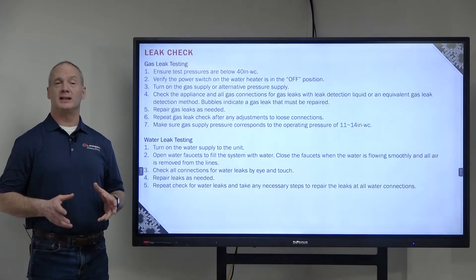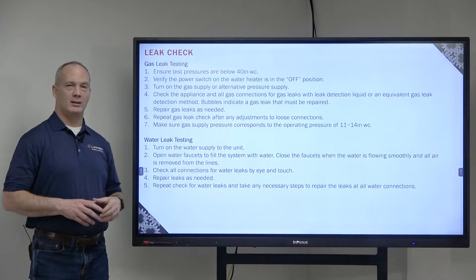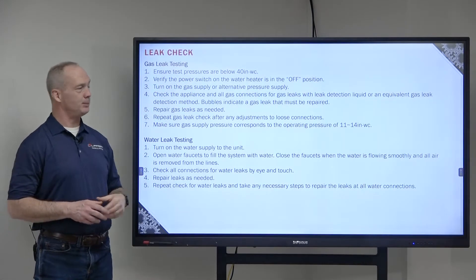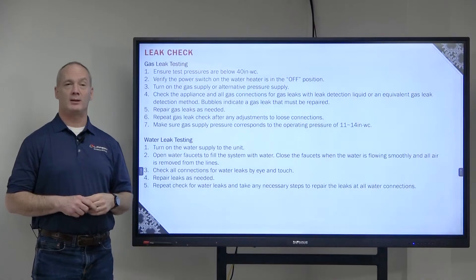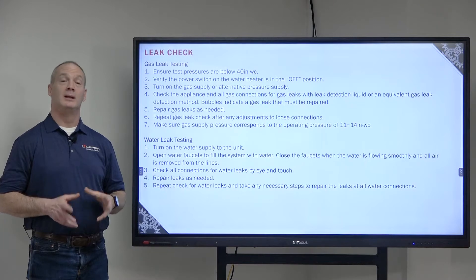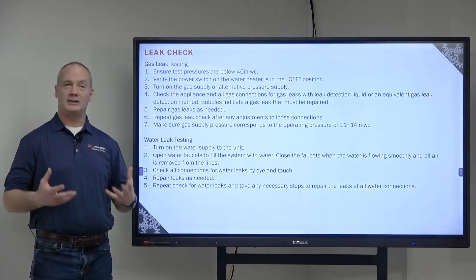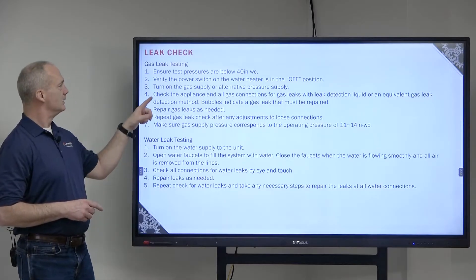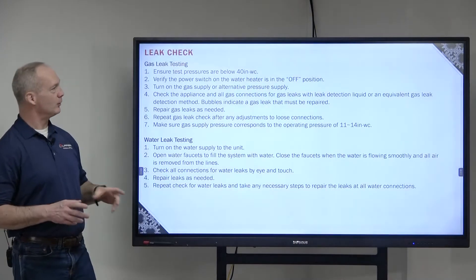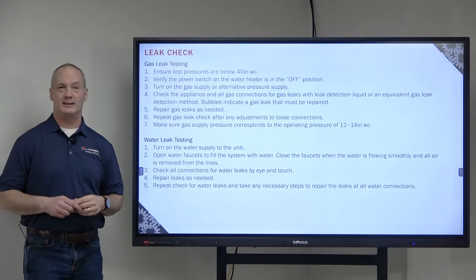Now that the installation process is complete, you're going to want to do a gas and a water leak test on your appliance. Start by making sure that the test pressures are below 40 inches of water column and then verify that the power switch is in the off position. Then you can turn the gas supply on and pressurize the unit with gas. Once that's complete, check your appliance and all the gas connections for leaks with a leak detection liquid or an equivalent gas leak detector.